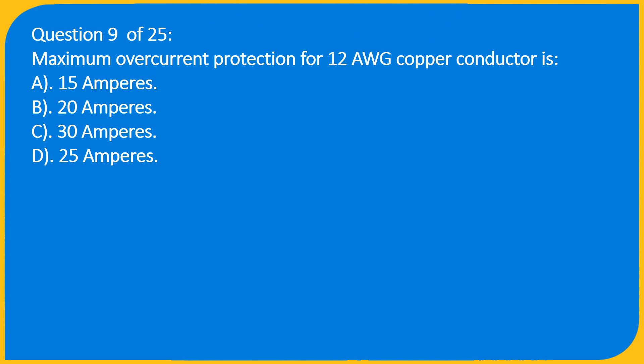Question 9 of 25: Maximum overcurrent protection for a 12 AWG copper conductor is? A. 15A, B. 20A, C. 30A, D. 25A. Answer: B. 20A.